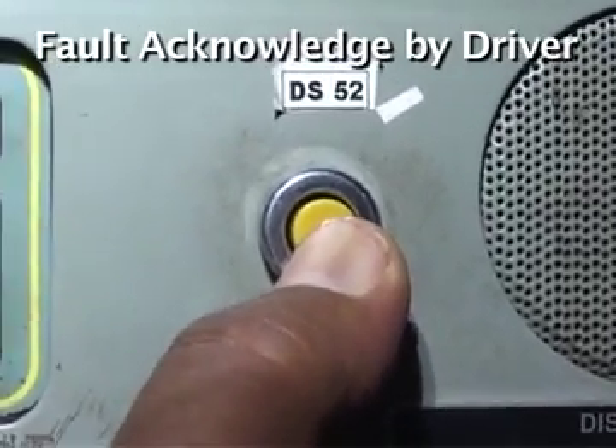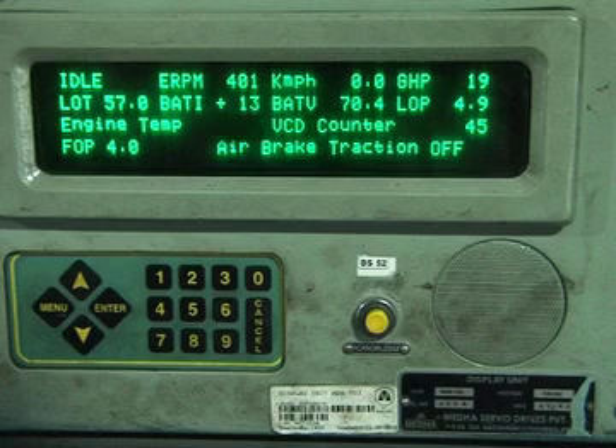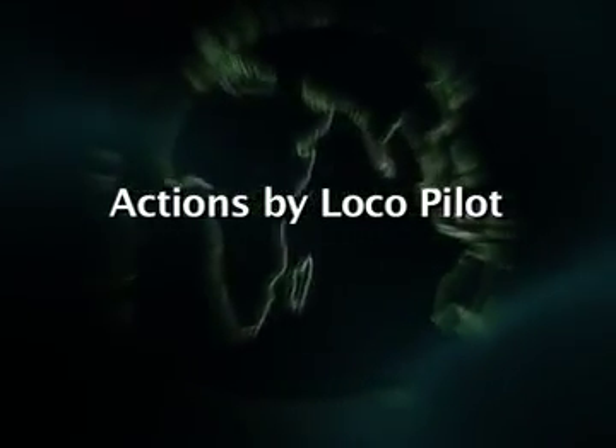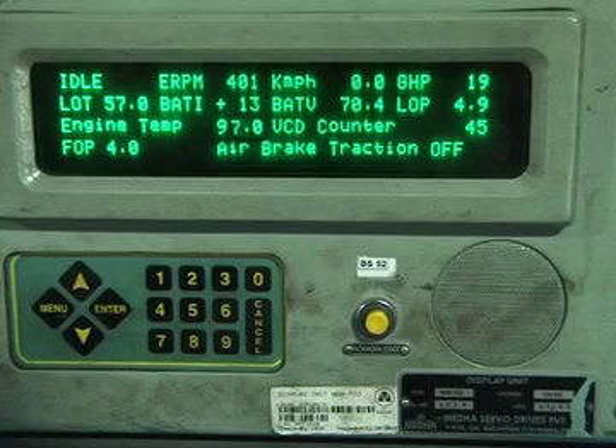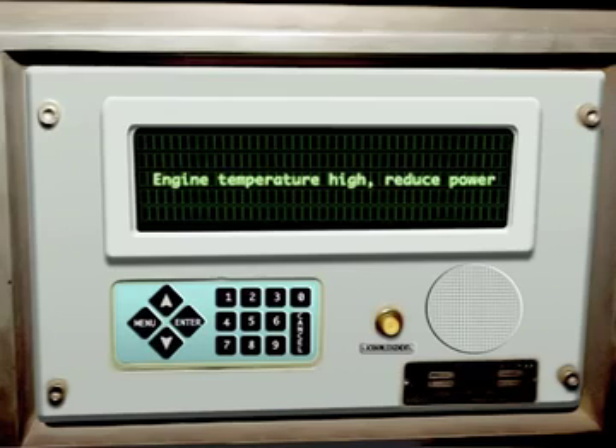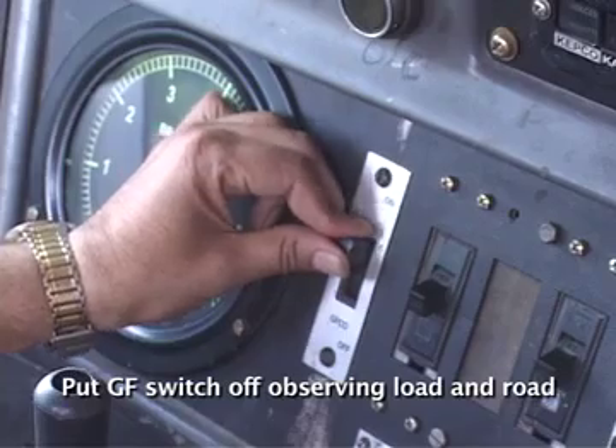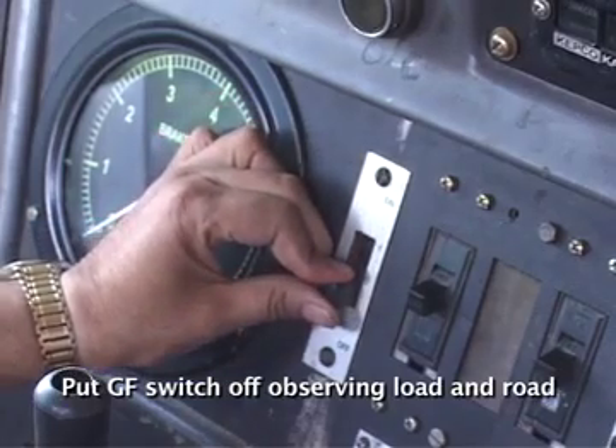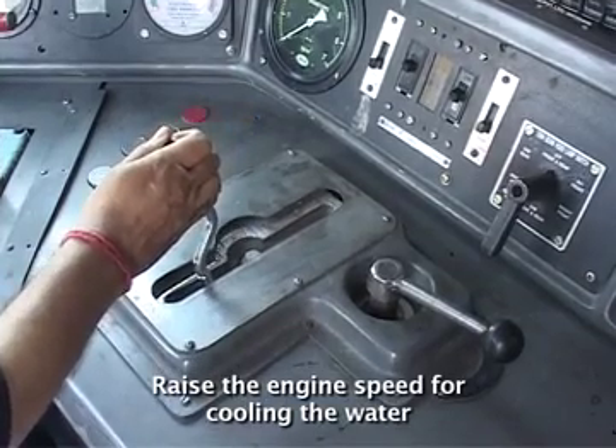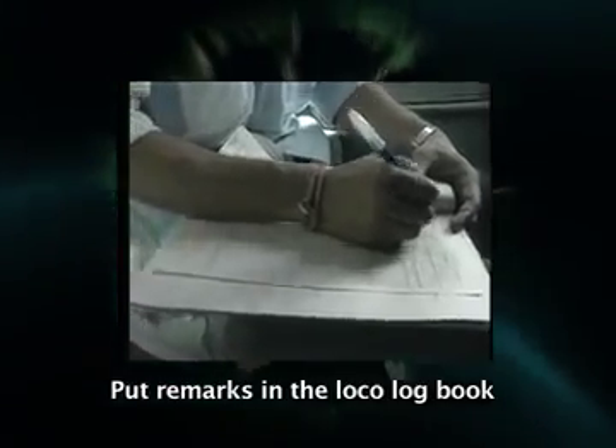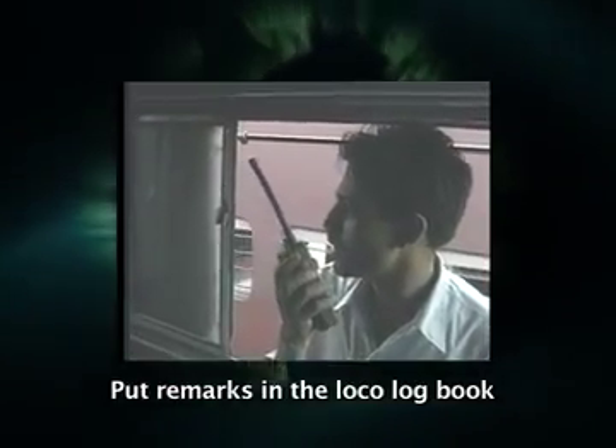Driver acknowledging fault. Probable cause: engine water temperature exceeding 95 degrees Celsius in display. Action by driver: check water temperature in display. Before this message comes as engine temperature high, reduce power. Immediate action: put GF switch in off, observing load and road, and raise the engine speed for cooling the water. Put remark in the loco logbook and advise PCOR, power controller.